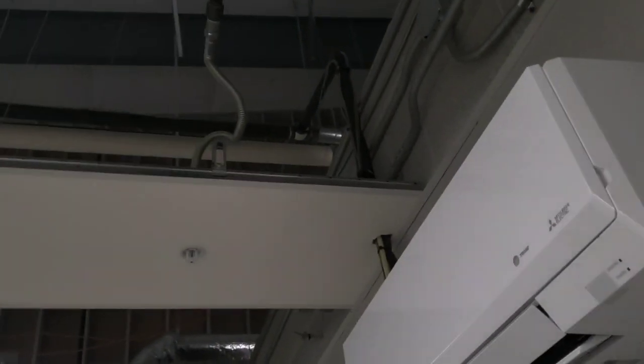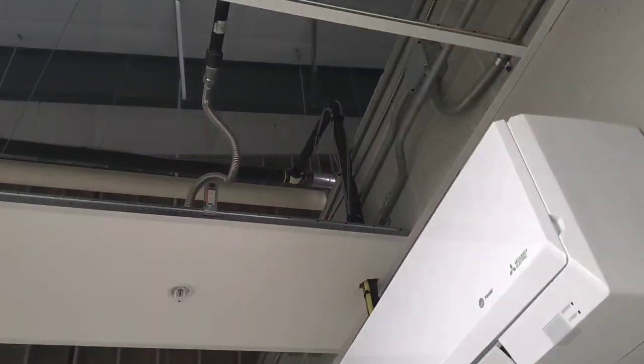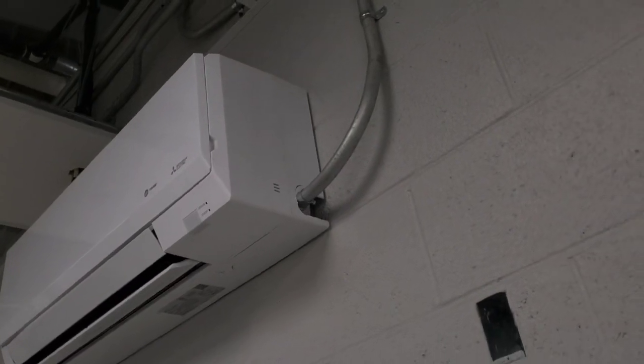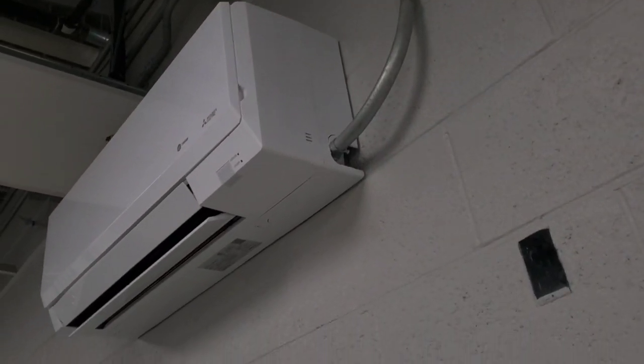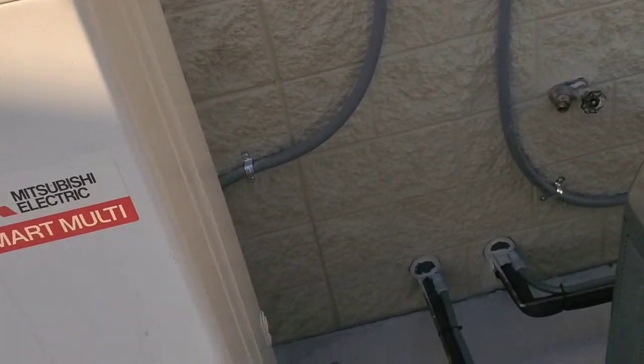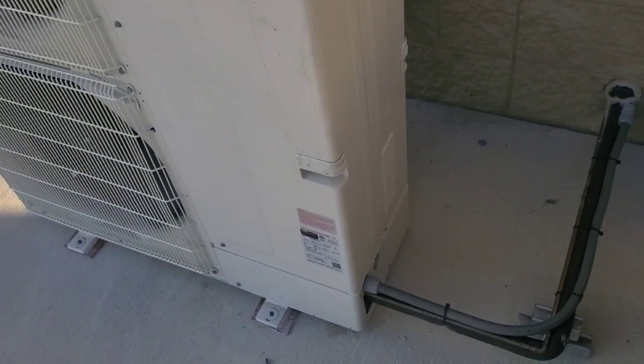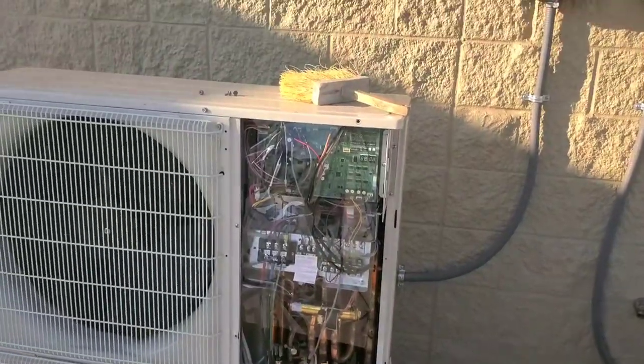And if you look up here above this one, you'll see a T, not a branch box. These heads have the expansion valve in the head. And that's a liquid line. What's wrong with that then? Why would that be an issue? Well, look at all this shit.